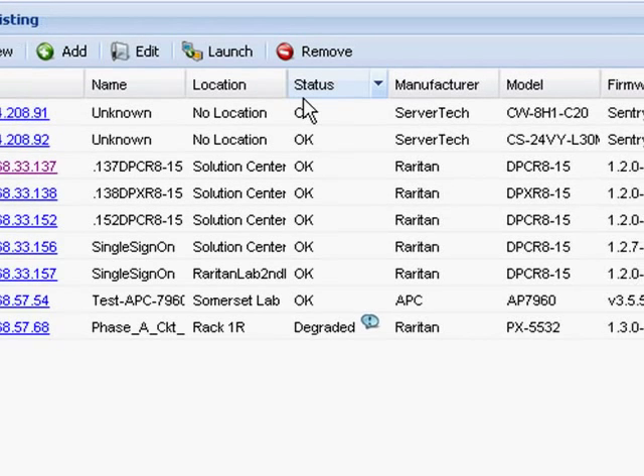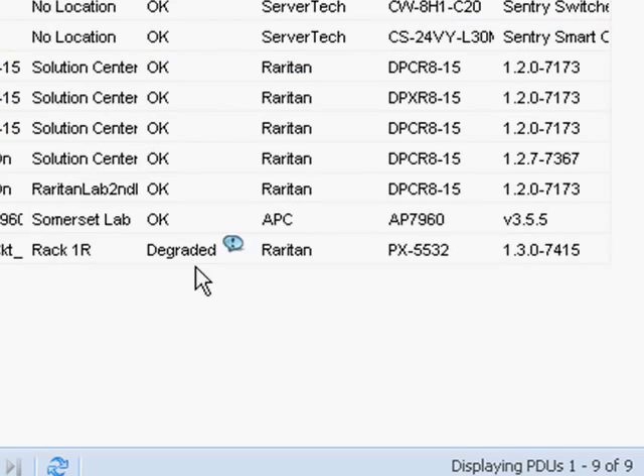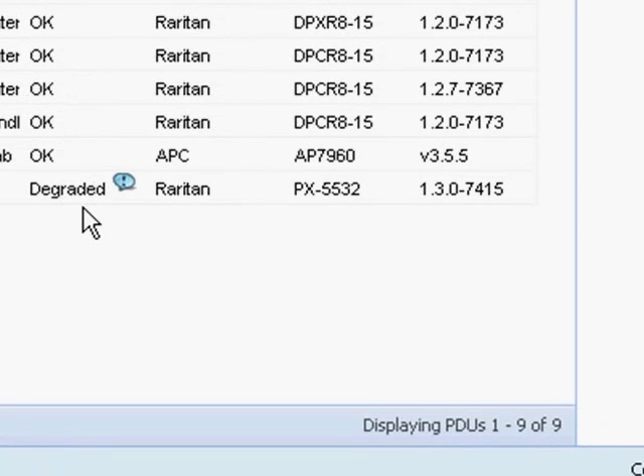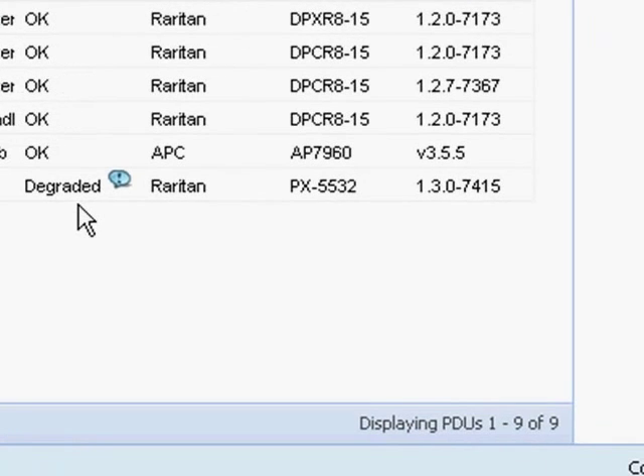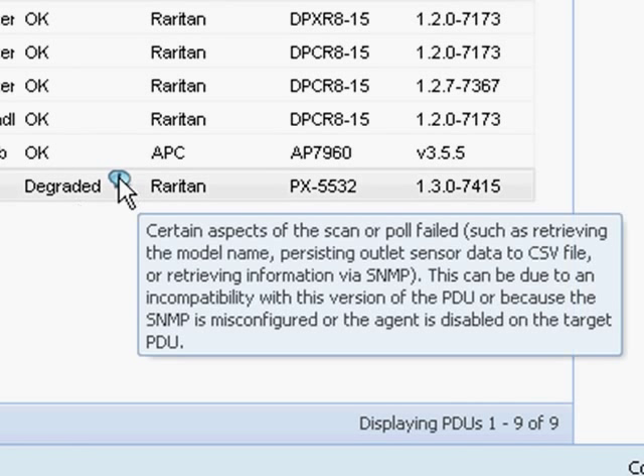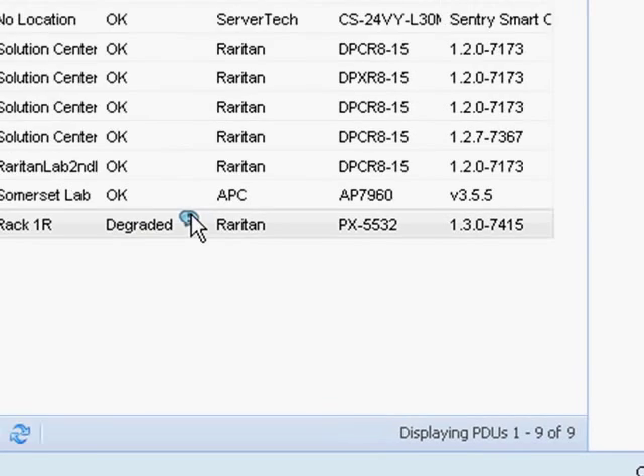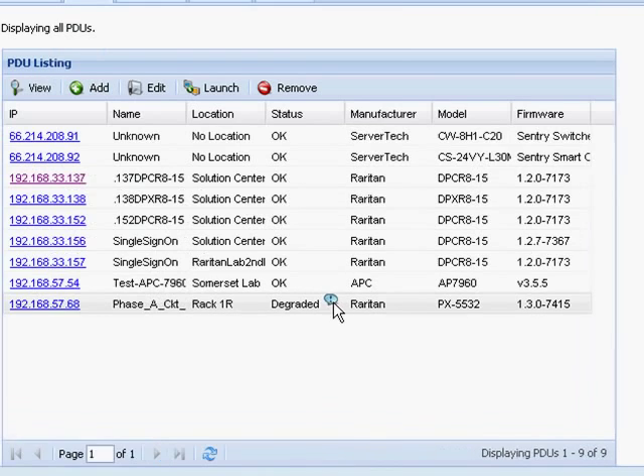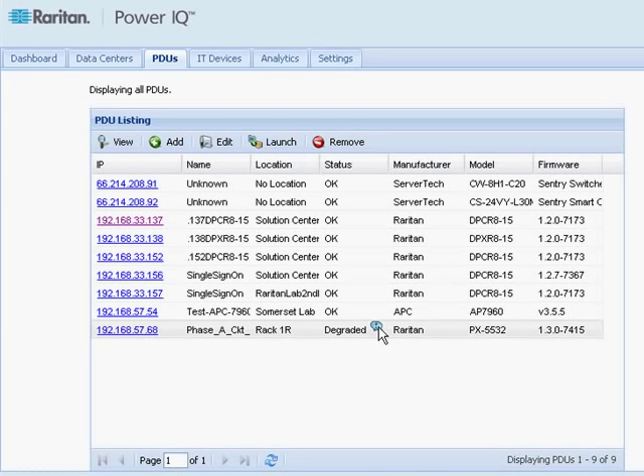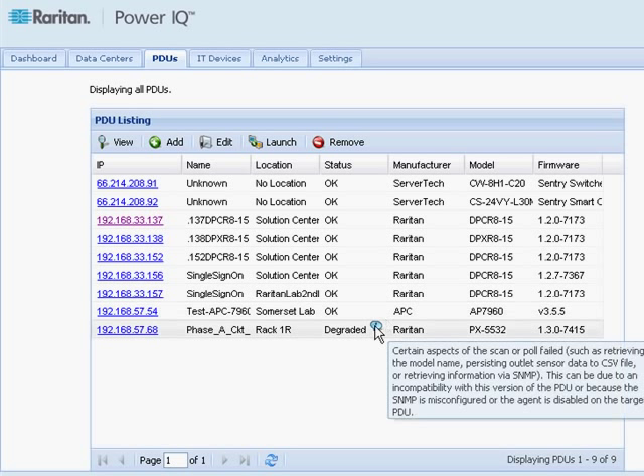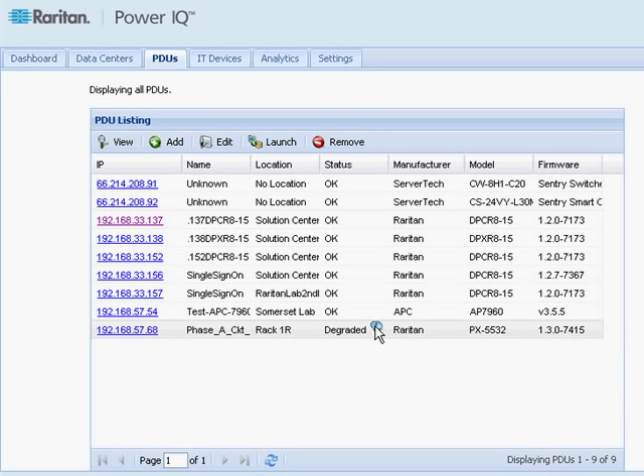If the status is not OK, such as Degraded, then I might have, I mouse over, and I get a just-in-time help. So in this particular case, it's giving me some error messages, and you would have to then react to those error messages. It might be that you don't have SNMP set up correctly, or this might be due to the communication path between PowerIQ and the PX is blocking SNMP communications.